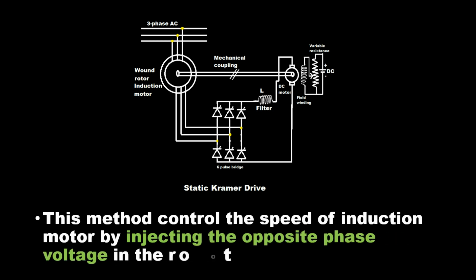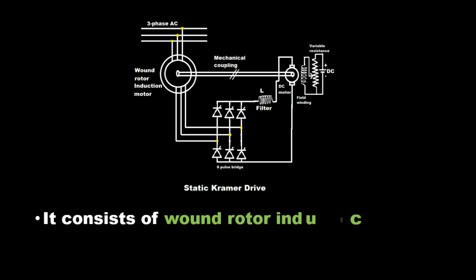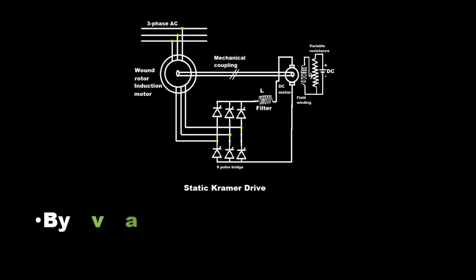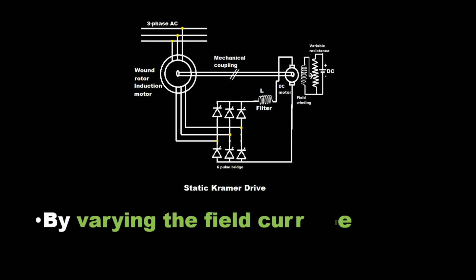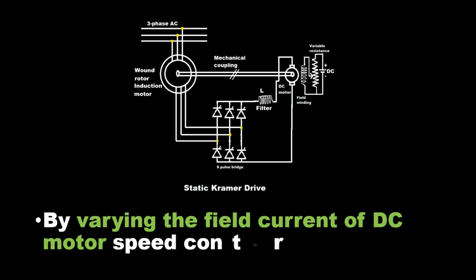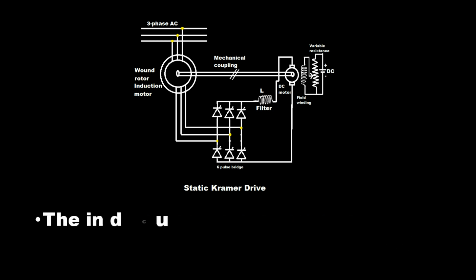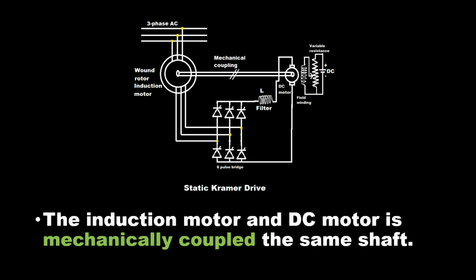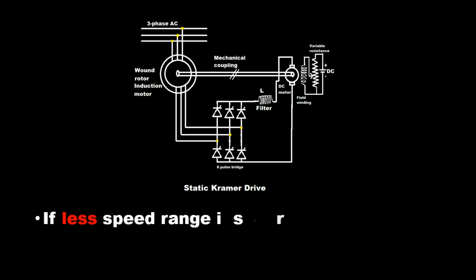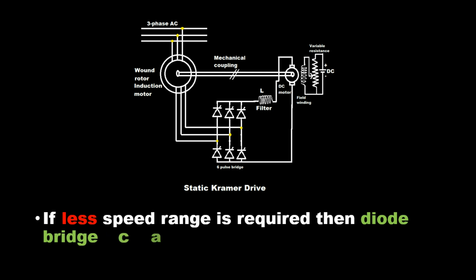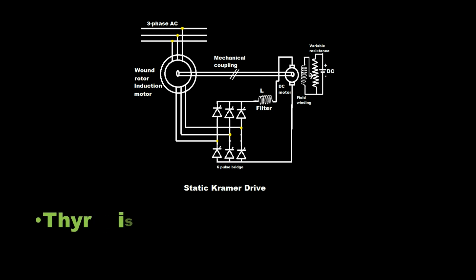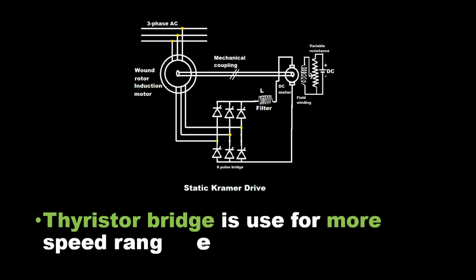This method controls the speed of the induction motor by injecting an opposite phase voltage into the rotor. It consists of a wound rotor induction motor, a smoothing reactor, a 6-pulse bridge, and a DC motor. Speed control is obtained by varying the field current of the DC motor. The induction motor and DC motor are mechanically coupled on the same shaft. If a smaller speed range is required, a diode bridge can be used in place of the thyristor bridge. A thyristor bridge is used for a wider speed range control.